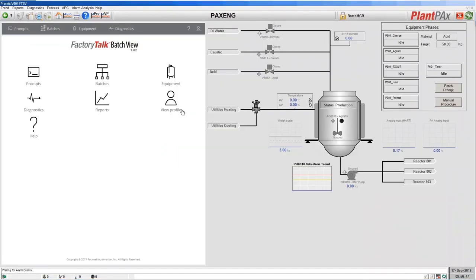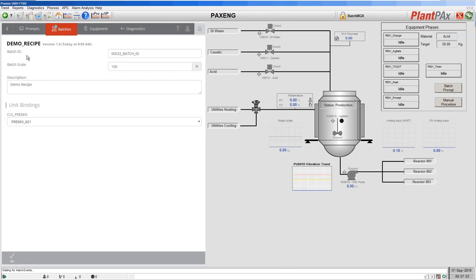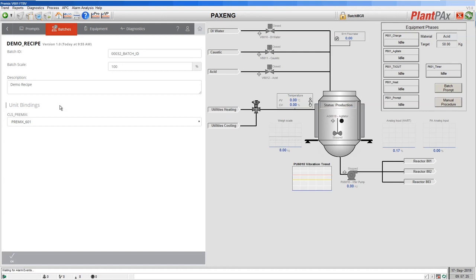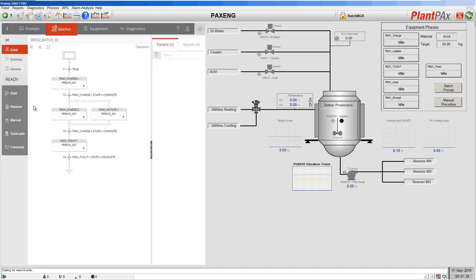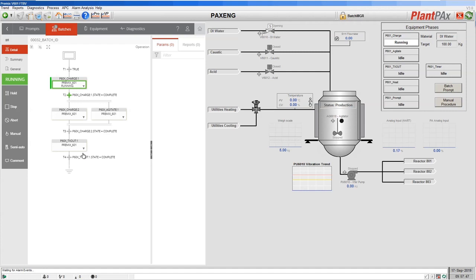Let's go and run our demo recipe in FactoryTalk Batch. We go back to our FactoryTalk Batch screen, go into our batches list, and now if we add our batch we can see that the demo recipe is now listed — because we released it. We can select that. The system has given it an automatic batch ID. It's asking us for batch scaling, but we didn't specify any of our parameters to be scalable so that will have no effect. We can see our recipe description, and because it's a recipe that can run on any premixer, we're being asked to select the premixer to use. Let's select the premixer we're looking at here on this graphic and select OK. Our recipe is now on the batch list. We can look at the details and now run it.